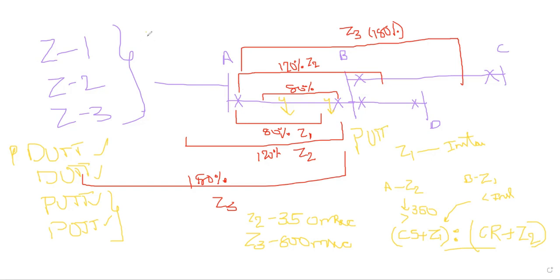And the other scheme is the POTT scheme, which is the permissive overreach transfer trip scheme. These schemes are generally rarely used. This scheme is maybe for short lengths, like 10 kilometers or less.